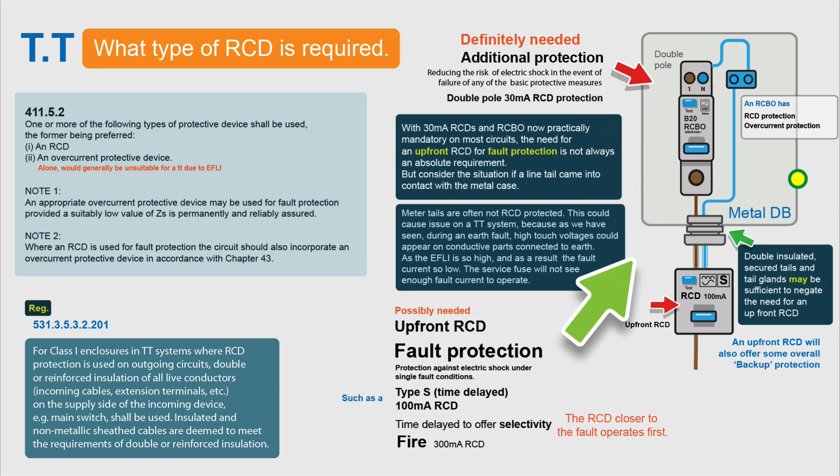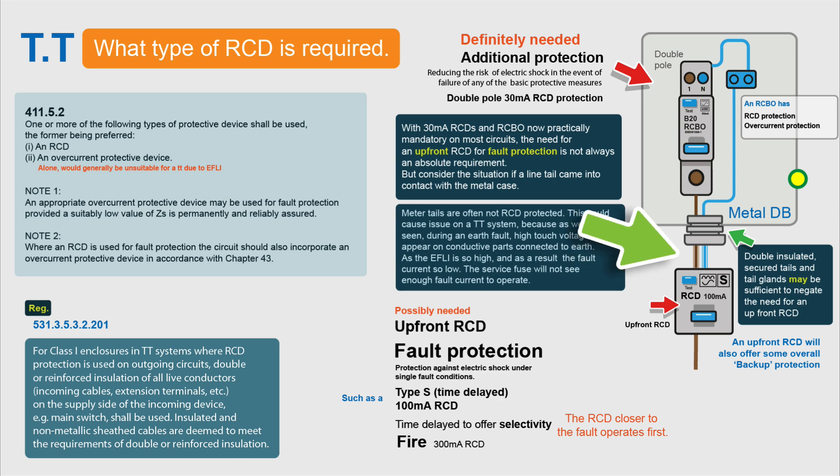Something to bear in mind is that if the consumer unit or distribution board is made of metal, there is potential for it to become live during a fault. We know the overcurrent protective devices won't operate because it's a TT system, and if there's no RCD that case could just sit there live. But there's guidance that if the meter tails coming into the consumer unit are in a proper gland, are double insulated, and are secured, there's very little chance of those tails becoming damaged and energising the consumer unit. So up-front fault protection is not necessarily required, but what's definitely needed is the additional protection for the outgoing circuits. The up-front RCD does provide some overall backup protection, but it depends on the installation what is required. That's your TT system — I hope it's been of some interest, and thanks for watching.